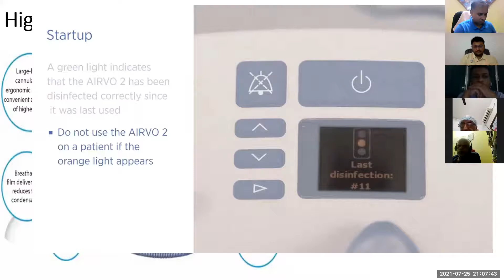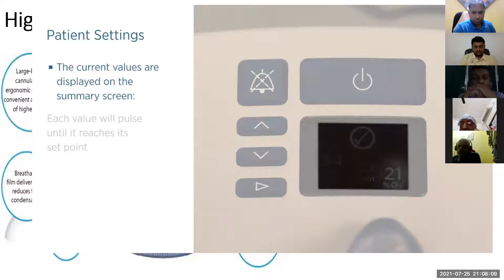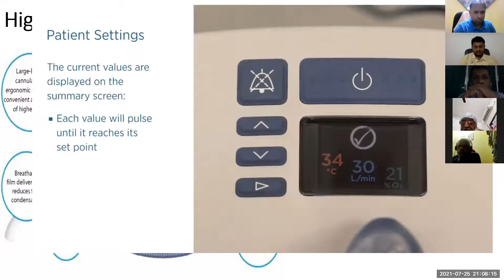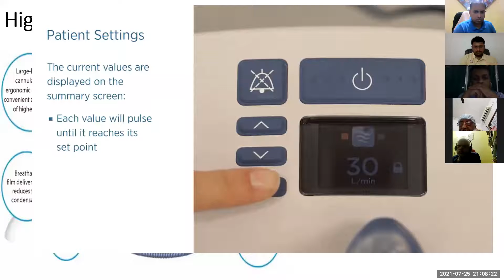After confirming the AIRVO 2 has been correctly reprocessed, you will need to adjust the patient's settings to match the treatment required. The current values are displayed on the summary screen: dew point temperature, respiratory gas flow rate, and oxygen concentration. Each value will pulse until reaching its set point. To make an adjustment, press and release the mode button to cycle through the set point screens until you reach the desired option.